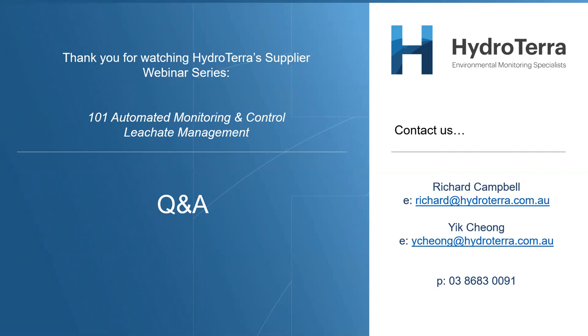We've got Mikhail back again. We had an overflow on our top dam recently. It was before the threshold was set up properly. So that was before the system was set up. When we install it, we notify the consultants that we're going to do some monitoring, and we have to watch it for a while before we know it's actually working properly. There was an incident where it overflowed because the level wasn't set up quite right, so we fixed that level threshold after that. But that was, you know, so-called teething issues.